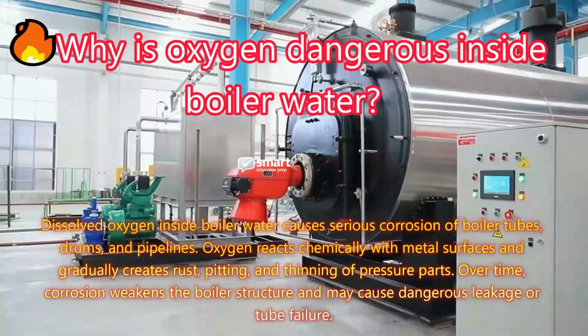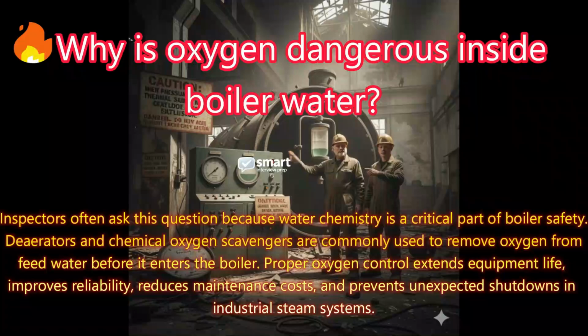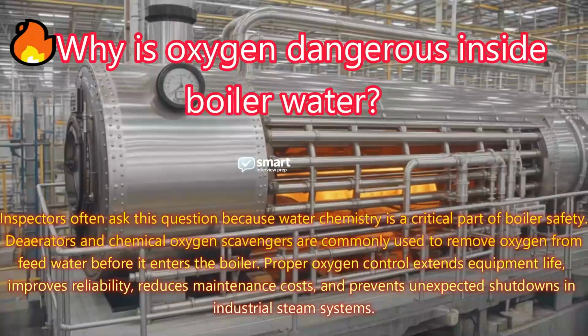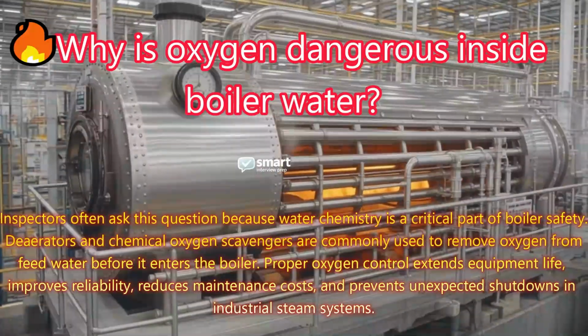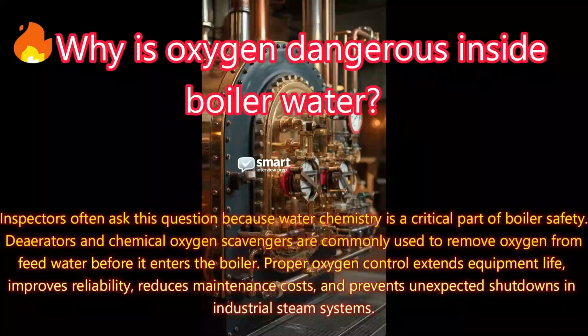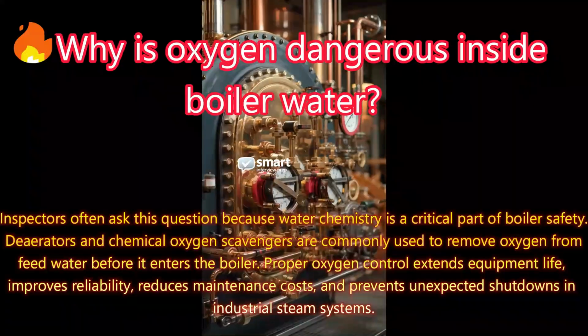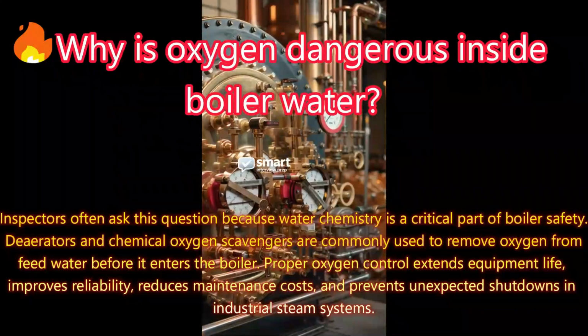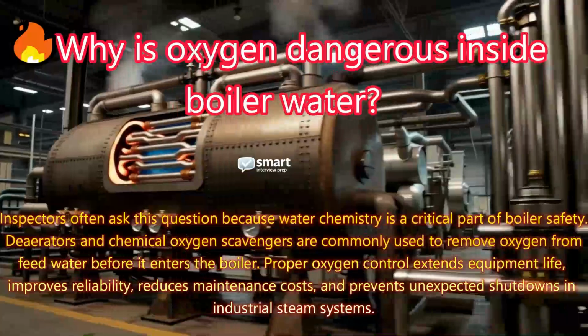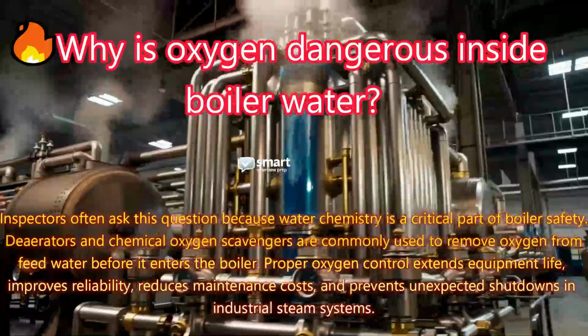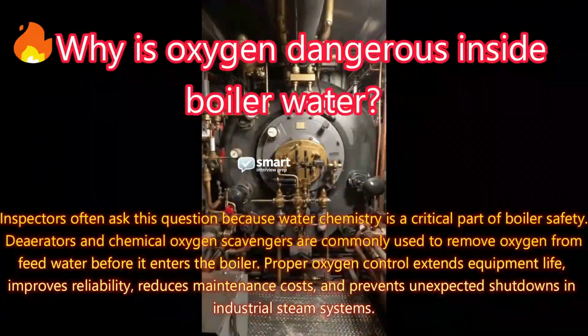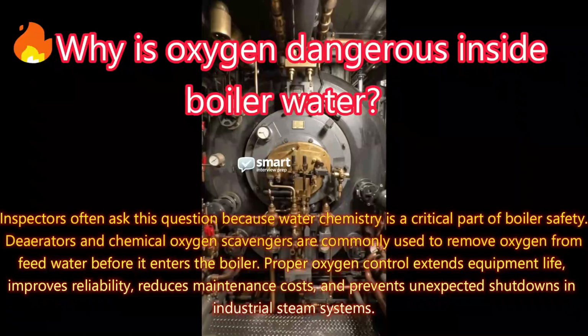Inspectors often ask this question because water chemistry is a critical part of boiler safety. Deaerators and chemical oxygen scavengers are commonly used to remove oxygen from feed water before it enters the boiler. Proper oxygen control extends equipment life, improves reliability, reduces maintenance costs, and prevents unexpected shutdowns in industrial steam systems.